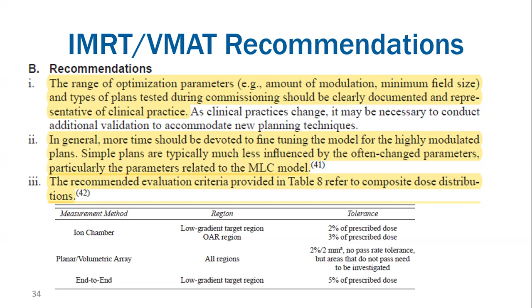They also recommend evaluation criteria. So basically, kind of what we did in a way: the ion chamber measurements, the planar and volumetric array measurements, and then also they recommend an end-to-end test in their treatment planning system commissioning.